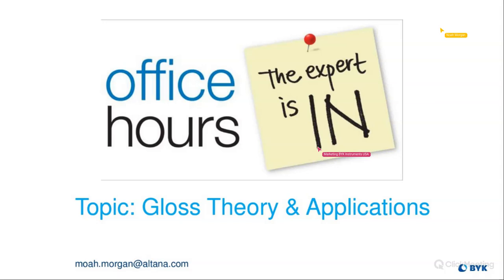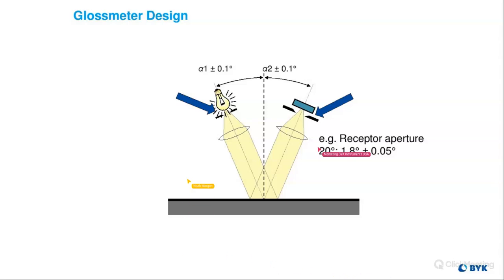Can you elaborate on what's the cause for when some samples do detect values and other samples don't? I think this is a bit of a repeat. Yes, I think I've spoken on it earlier. Typically, you shouldn't have a result that isn't anything. What we're basically doing with the internals of this instrument is just measuring the light that goes from here, which is 100% of light. It hits the surface, and then this picks up all the light that gets reflected back.